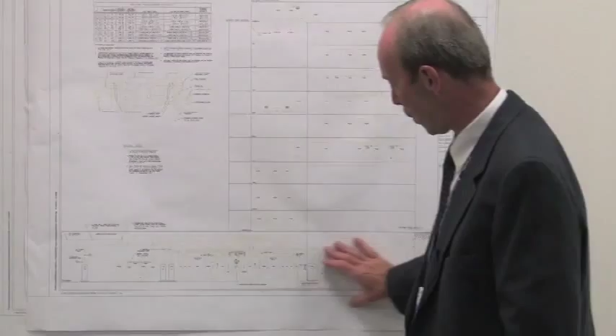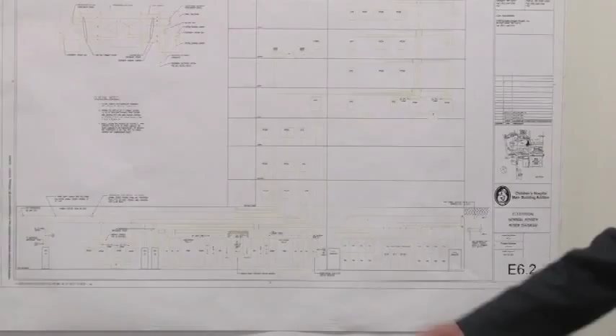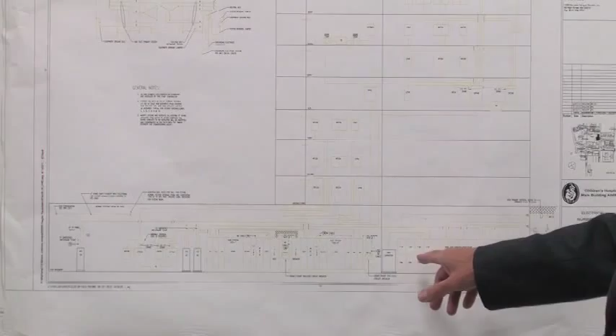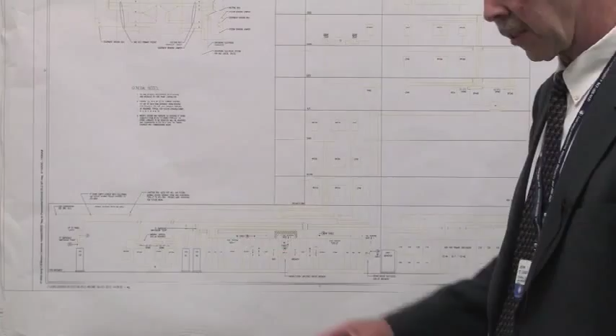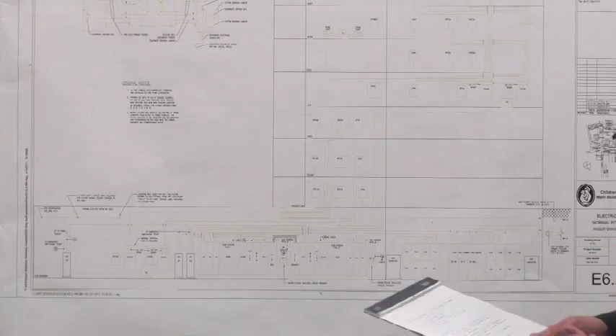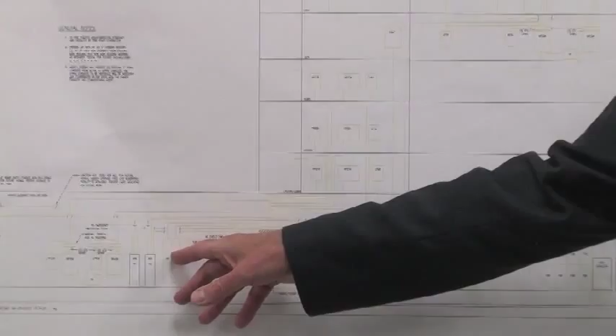This is a riser diagram for the normal distribution system. Again, everything's down in the sub-basement level. After you come off the primary of the new gear, you've got 2 1500 kVA unit substations oriented in a main-tie-main configuration with an overhead tie. These are 1500 kVA dry types with fans, giving you 1500/1995 kVA. You've got dual primary switches on either end, so you've got primary selectivity.